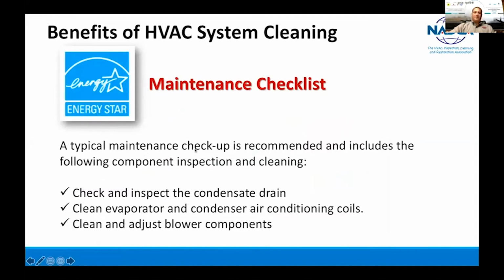A typical maintenance checkup is recommended and includes the following components: component inspection and cleaning. This is by the Energy Star. Check and inspect the condensate drain, clean evaporator and condenser air conditioning coils, clean and adjust blower components.